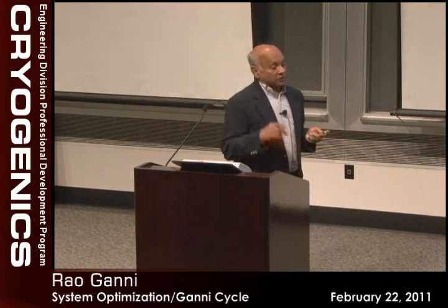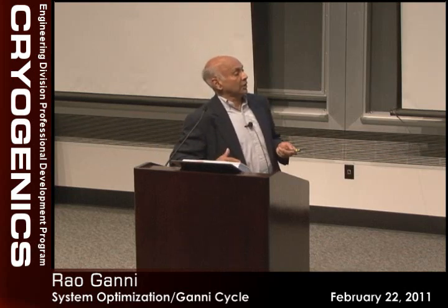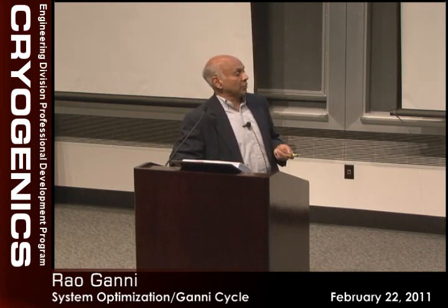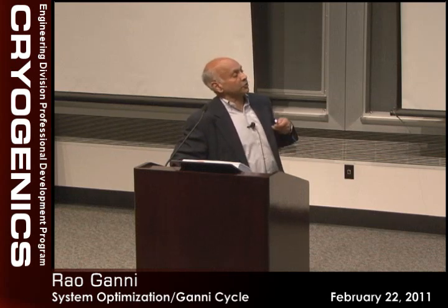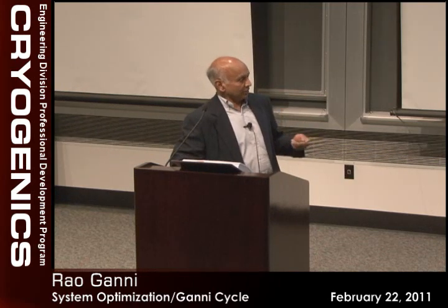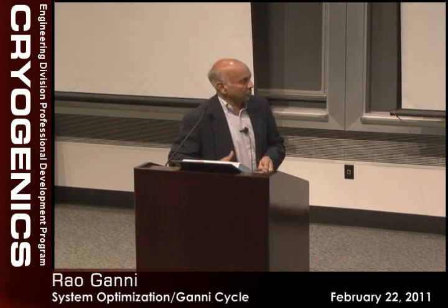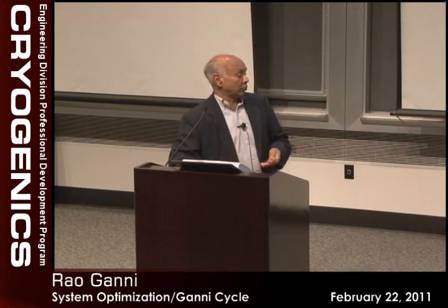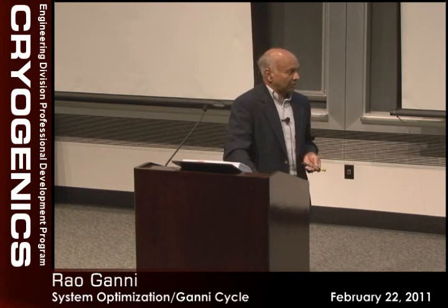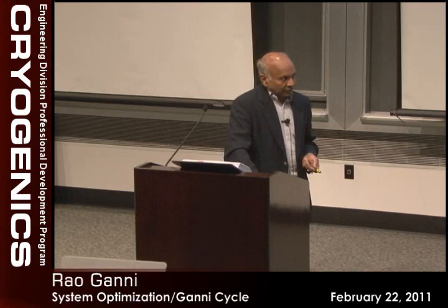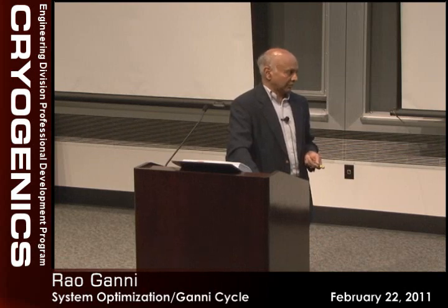Existing, the other one at the CHL2 is basically the compressors. We do not have compressors that can go above 55% isothermal efficiency today. Unless we push the compressors to the next level, that's where Pete's PhD project is, and that's where we are. We think the next breakthrough has to come from the compressor, because we're throwing away half the availability at the compressor level right at the start. Do you think the biggest pole in the tent right now is the warm compressor? Warm compressor. That is by far the next contributor.